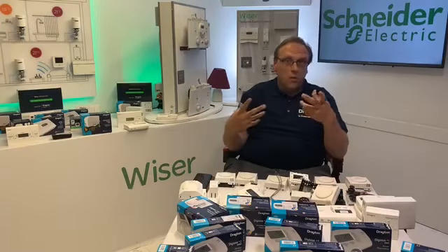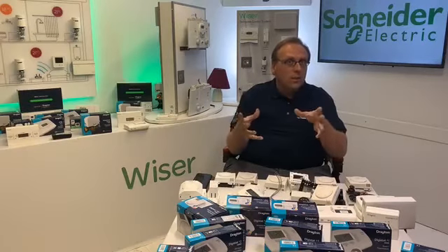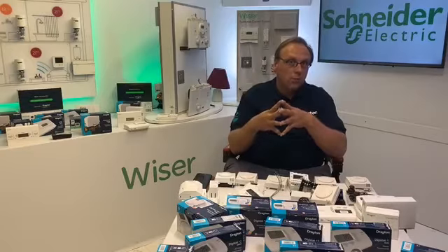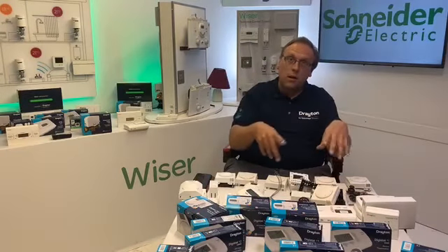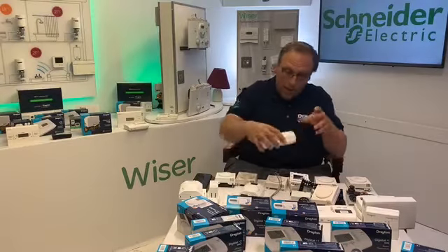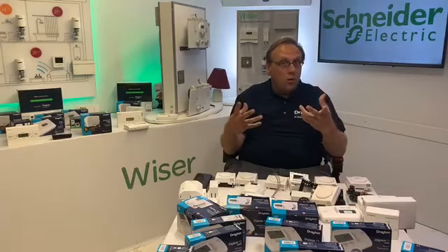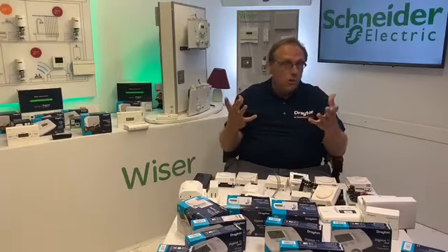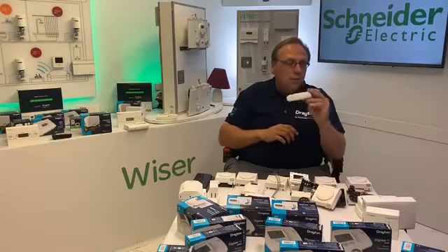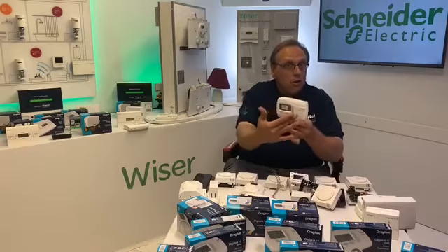It's just that you've got the luxury of being able to walk around the property with it. So if it's not convenient to get wires to it, or the customer wants to move it around, you would need to fit an SCR, and then your actual stat is remote. But again, if you're looking at replacing an RF control, so say if you have a Digistat transmitter, this part that goes faulty, if it's a Plus 2, like this one is, you need to make sure it's a Plus 2 RF that you replace it with.